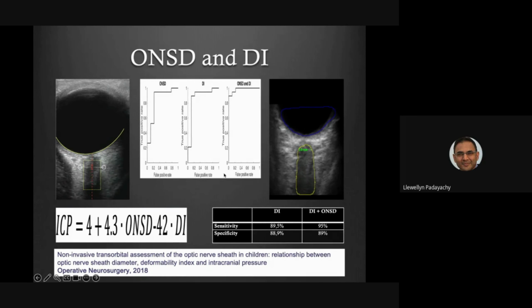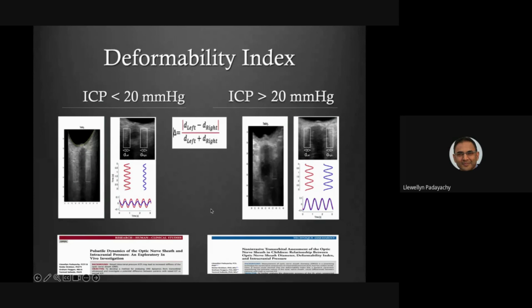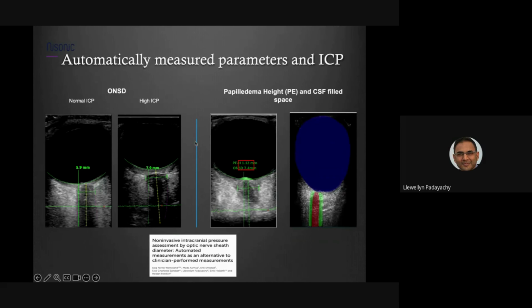And if you use that sort of pulsatile measurement of the elasticity of the sheath and you punch it into a regression formula, it's actually a pretty good predictor of ICP. You can look at ONSD, and then once we combine these two, you can see we've significantly improved that. So effectively, the technique involves 10-second videos collecting movement around the sheath. These are punched into an algorithm, and for those of you interested, we've published several articles on that. And it's quite good for picking up dichotomized ICP, so above and below 20 millimeters of mercury. This work was advanced on significantly. There are several publications now from Norway where we tried to standardize the technique using a machine learning algorithm.